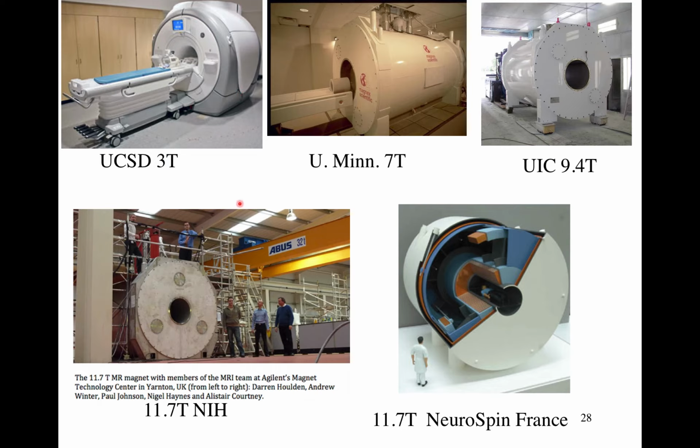And then there are more experimental systems in which, this 11.7 T Neurospin, so it's like 4 times the magnetic field of this one that comes out of the box, generating a much higher amplitude signal, right? But it also comes with some technical challenges. But I think Dr. Liu will talk more about that. 7T magnets are now fairly common. You can also buy these off the shelf from almost any manufacturer now as a 7T system.